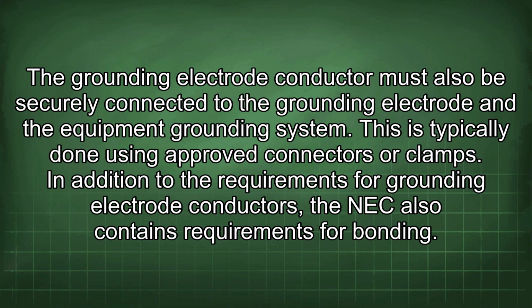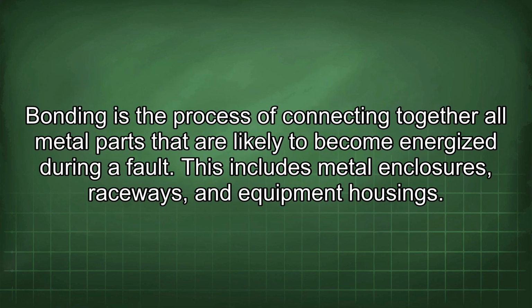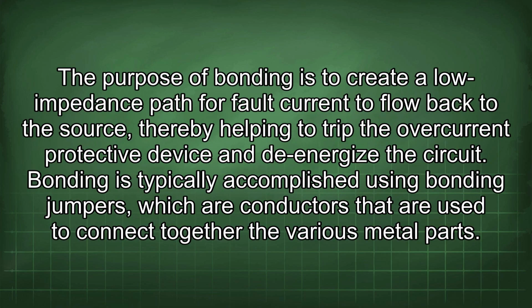In addition to the requirements for grounding electrode conductors, the NEC also contains requirements for bonding. Bonding is the process of connecting together all metal parts that are likely to become energized during a fault. This includes metal enclosures, raceways, and equipment housings. The purpose of bonding is to create a low impedance path for fault current to flow back to the source, thereby helping to trip the overcurrent protective device and to de-energize the circuit.